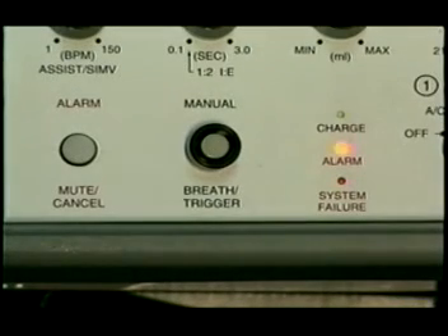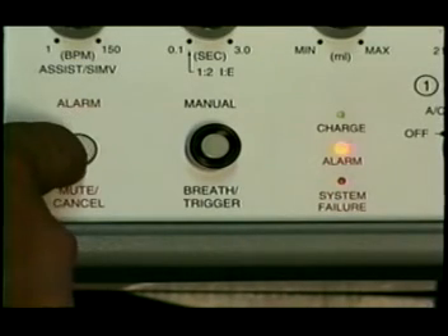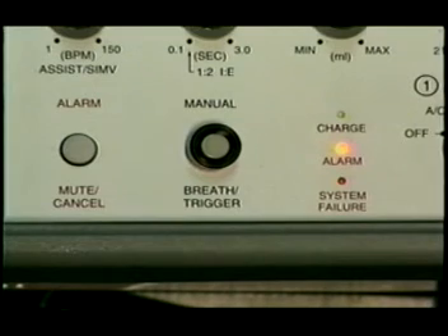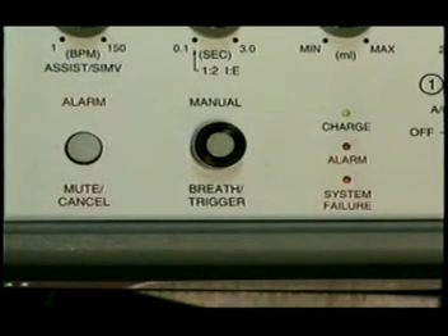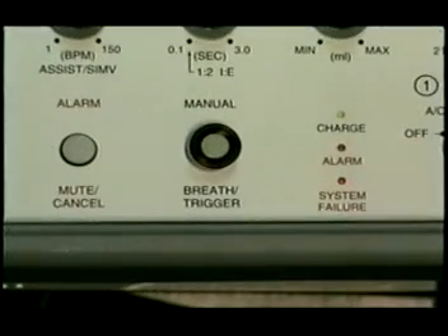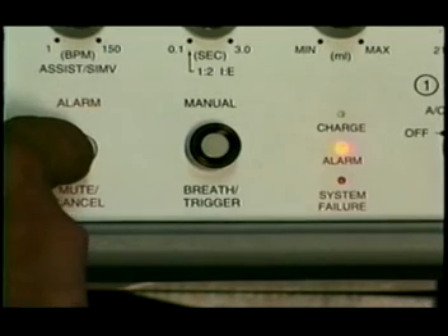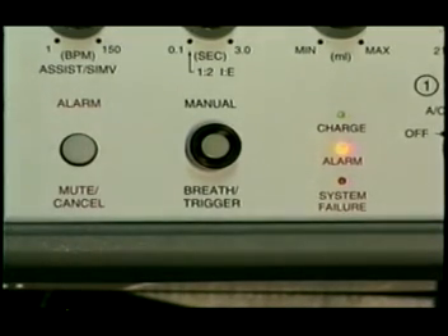The alarm indicator is a red LED that flashes on-off when an alarm is not muted, stays on continuously when the alarm has been muted, and is accompanied by a pulsing tone that is canceled during alarm mute periods. It activates for all alarm conditions except a system failure alarm. The alarm mute cancel push button switch will mute an audible operating alarm signal, or cancel an advisory alarm signal, or cancel specific alarms such as apnea or external power fail. A typical mute lasts for 30 seconds. However, battery and power alarms are muted for longer periods.